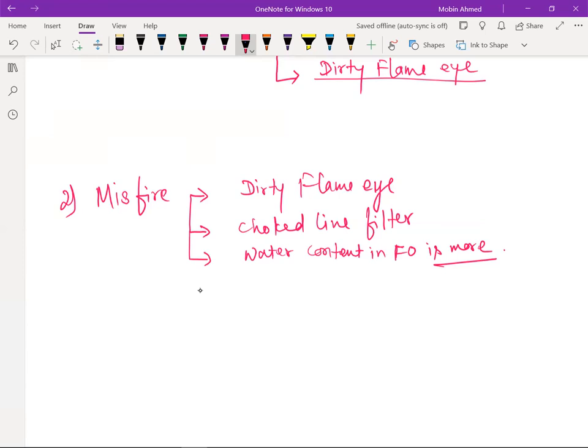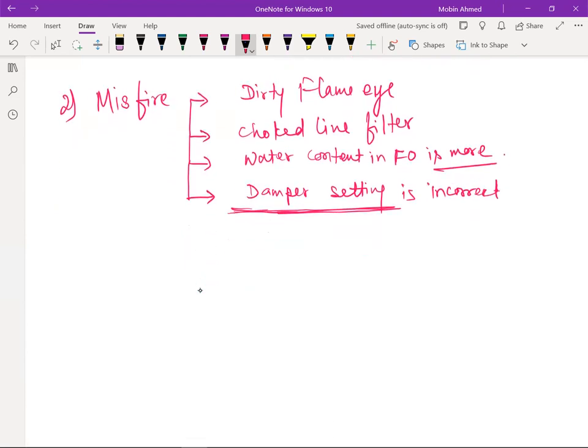One more problem that will come is with your damper setting. Damper setting is incorrect, because as soon as the damper is going to open, you will find the flame is gone, misfire. So this is a problem. Do not misadjust this damper. During commissioning it is adjusted, and people are doing many nonsense things with this damper. If you do not know about the damper, don't do anything. That is the best way to avoid it. At least you are not going to have the suspect. Incorrect damper setting should be the last option, after you have done everything else. Most of the time, your problem is not with the damper or the system but with this.